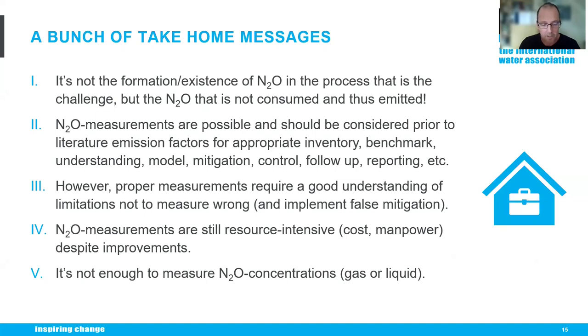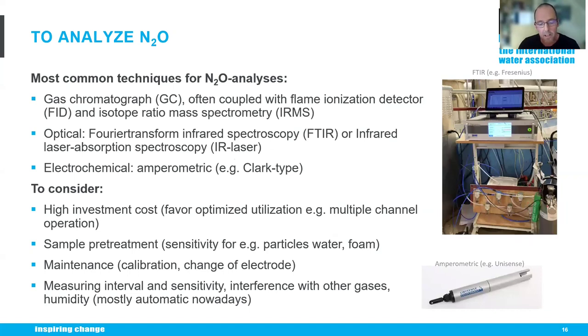For example, one instrument we use has a multi-channel analyzing feature allowing six different sample points to be analyzed simultaneously, given its fast response time, making measurements more cost efficient. You also need to consider sample pre-treatment, maintenance, calibration, and electrode changes for water sensors. Important aspects when investing in an instrument include measuring interval, sensitivity, and interference with other gases. Nowadays, most analytical instruments can adjust for these automatically — a big difference from ten years ago when everything had to be done manually.